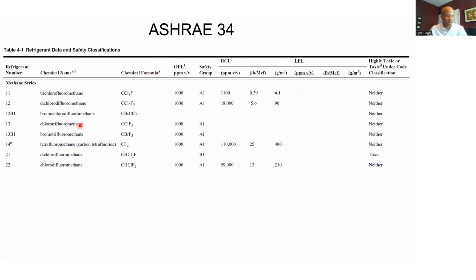So this is out of ASHRAE Standard 34. The same exact table exists in the International Mechanical Code. It exists in the Chicago Mechanical Code, and pretty much every mechanical code cuts and pastes the ASHRAE table into their code. I cut the table off at R-22. It goes beyond that, but I cut it off for the moment so we can digest it real quick. Here's RCL, refrigerant concentration limit. It's expressed in three different types of units. The one that I personally have used historically is pounds per million cubic feet. I don't care about metric things where I'm at, so that's what I've done. And for the lower flammability limit, there's nothing in the table because none of these things were flammable.